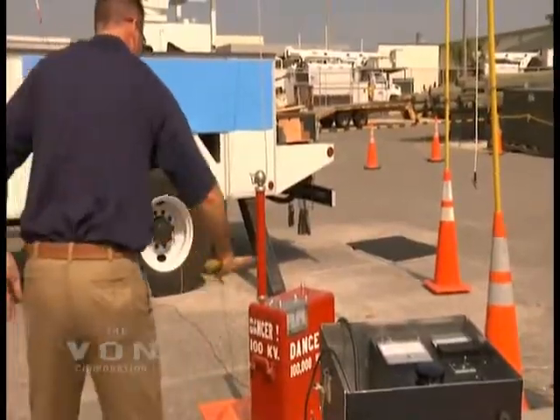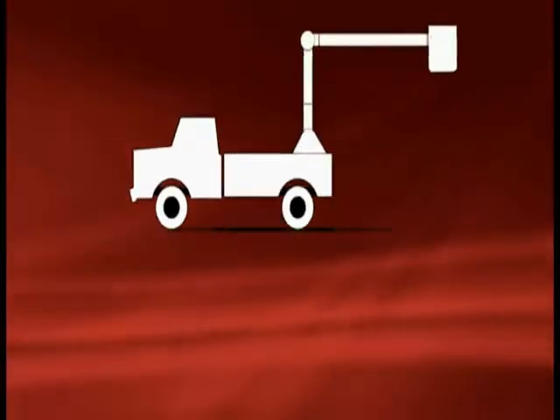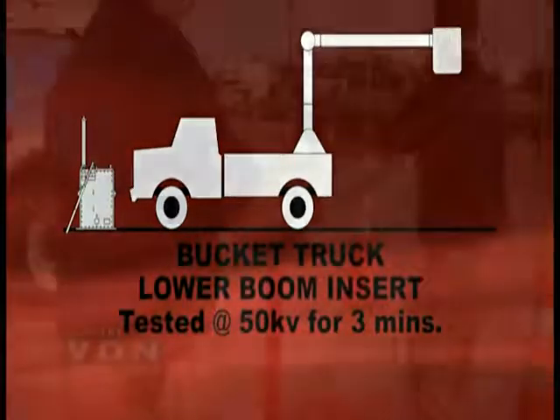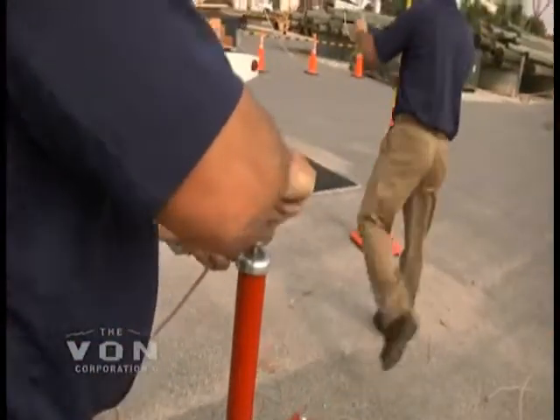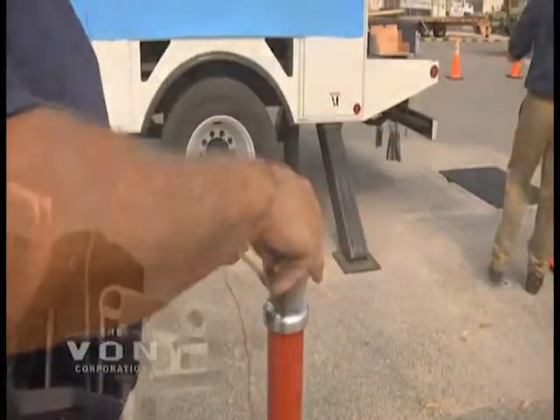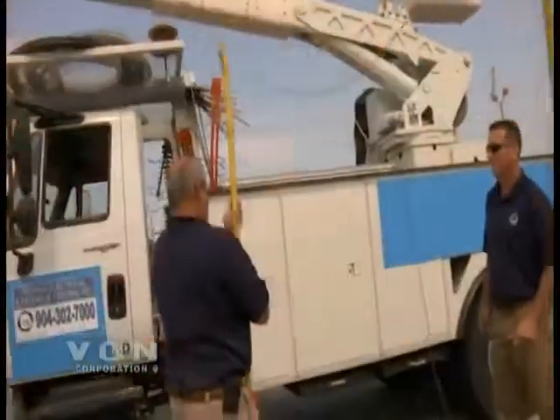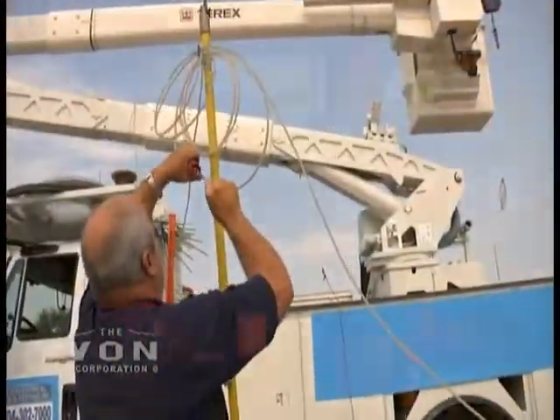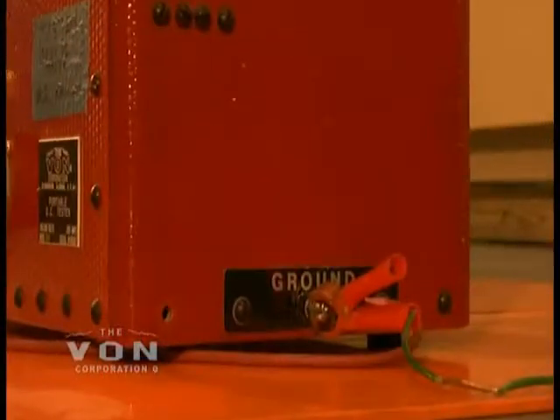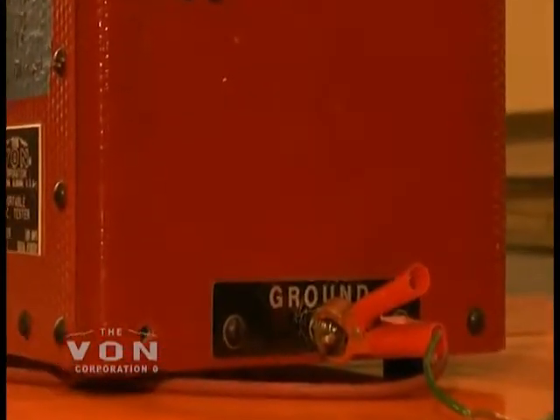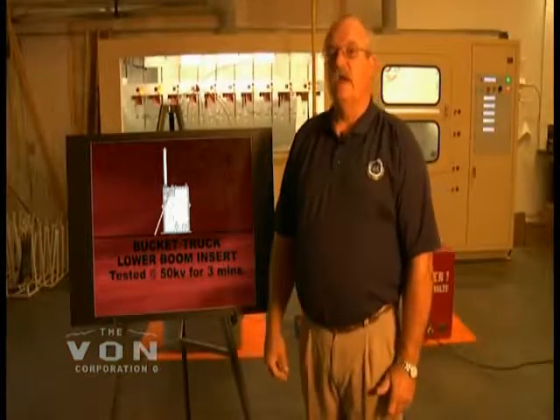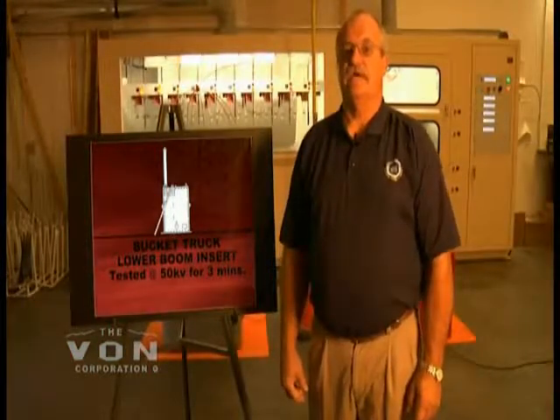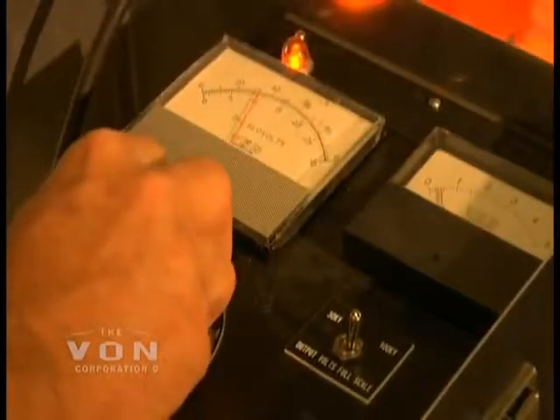Now we're going to test the lower boom insert without moving the truck. We're going to disconnect the upper boom lead and tie it up so that it is insulated from anything else, energize the boom of the lower chassis insulator, and connect the ground to the return ground of the unit. The chassis insulator protects ground personnel in the event the knuckle comes in contact with an energized line. This test is to be performed once every 12 months at 50,000 volts and not to exceed 100 microamps.